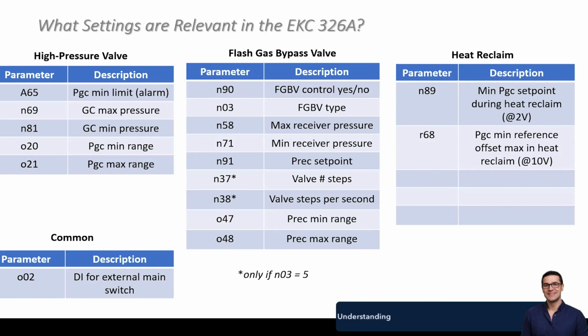We've got them grouped here. We have this documented if we ever need to get it out to someone, grouped based on function: high pressure valve, flash gas bypass valve, heat reclaim, our optional functionality there. And if we had something like a phase loss monitor wired to those first two terminals on the EKC, we also have a parameter that would let you tie that into the pack controller to use it the same way.